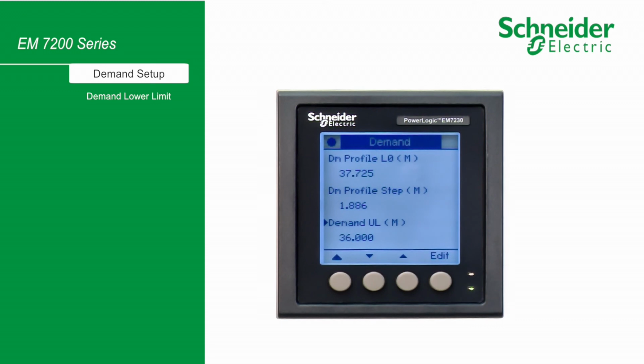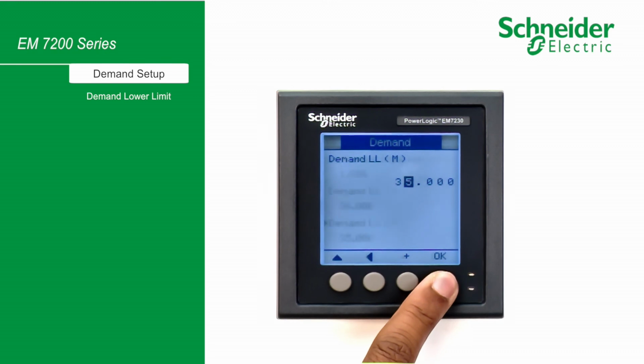Once you are done with the setting for upper limit, next step is to set the lower limit values. The significance of this feature is to reconnect the load whenever the demand falls back below the lower limit range, and this could happen within the demand cycle itself. You can choose 10 to 99% of upper limit as lower limit values. Let's select 35 MW as a lower limit in this case.